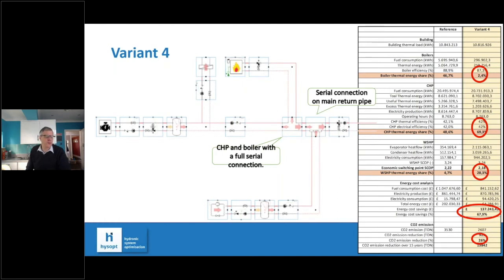So this is the final iteration of that concept design, where we've made further hydraulic changes to the way everything's linked together. We've got the heat pumps now running connected to the return flow of the primary side, and we've changed the connection between the CHP and the boilers as well. You can see on the right-hand side the overall impact: reducing the annual energy costs against the initial design by about 67-68%, and 26% in carbon emissions. The CHP is doing about 70% of the load, the heat pump around 30%, with a small top-up needed from the boiler.